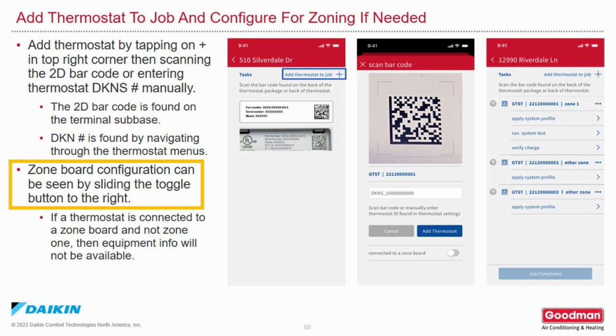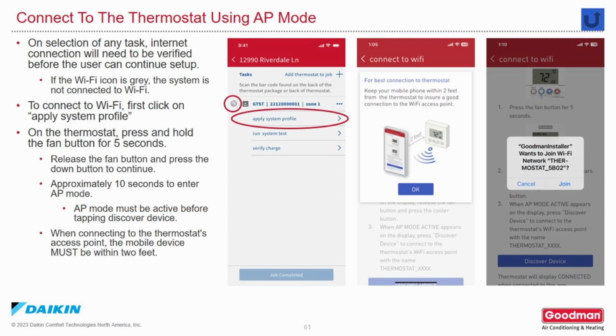Zone board configuration can be seen by sliding the toggle button to the right. If the thermostat is connected to a zone controller but not Zone 1, then the equipment information will not be available. Connect to the thermostat using AP or auto programming mode. When you select any task, internet connection will be verified before the user can continue the setup. If the Wi-Fi icon is gray, the system is not connected to the Wi-Fi.